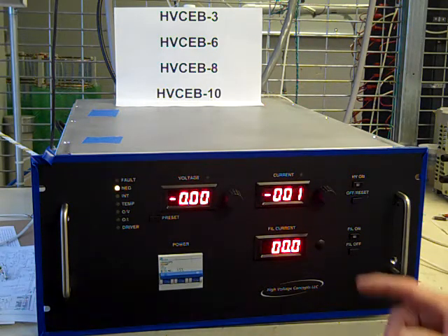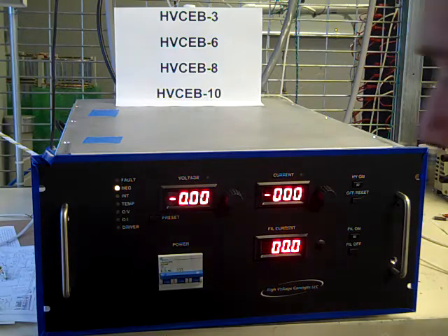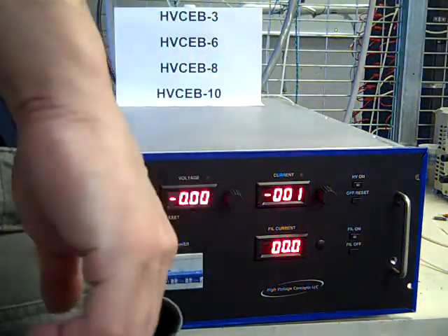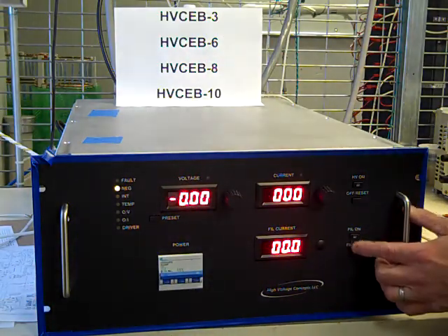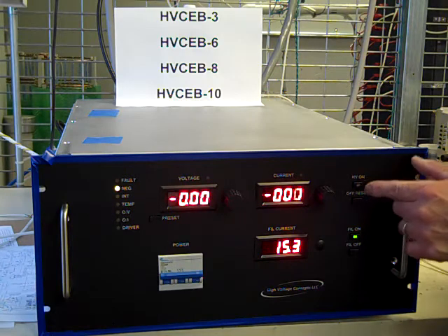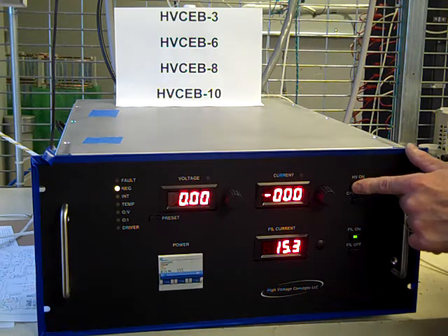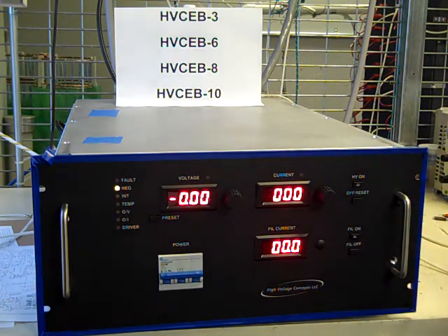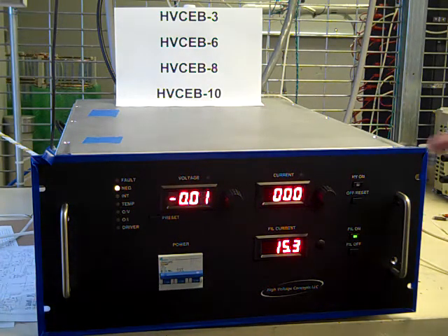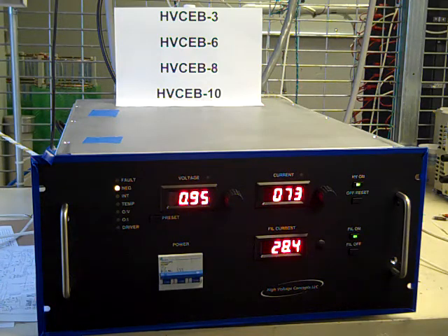This is to counter your magnet, which usually doesn't drift that much. So right now I'm going to ground the pin. And now if I try to turn on high voltage, I can turn the filament on, but you'll see I'm on remote mode. I can't turn high voltage on. Okay, so now we're going to apply high voltage via remote. Filament comes on, and then 6 to 7 seconds later, we end up with high voltage on.